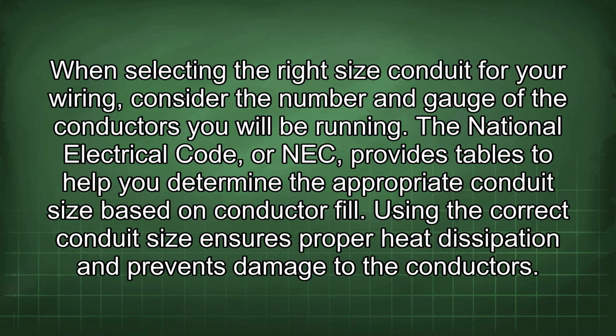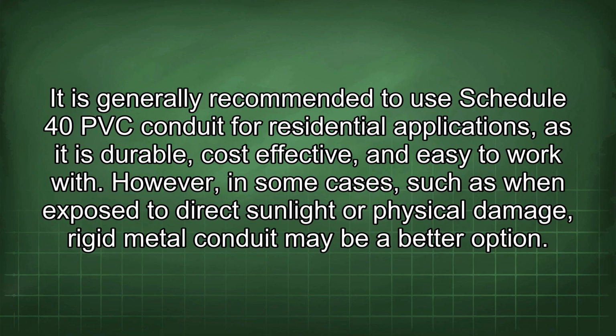When selecting the right size conduit for your wiring, consider the number and gauge of the conductors you will be running. The National Electrical Code, or NEC, provides tables to help you determine the appropriate conduit size based on conductor fill. Using the correct conduit size ensures proper heat dissipation and prevents damage to the conductors. It is generally recommended to use Schedule 40 PVC conduit for residential applications, as it is durable, cost-effective, and easy to work with. However, in some cases, such as when exposed to direct sunlight or physical damage, rigid metal conduit may be a better option.